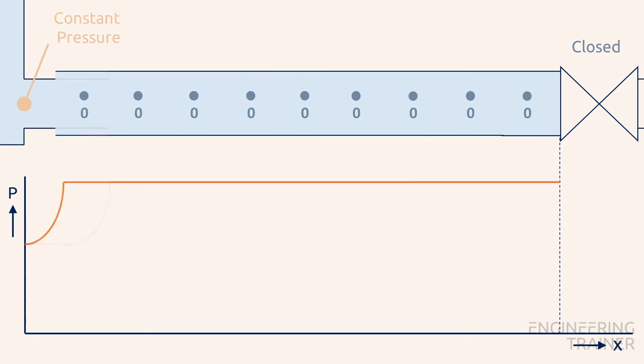Once the pressure wave reaches the reservoir it cannot continue because of the constant pressure from the tank. The situation now shows a higher pressure in the pipe than that what is expected from the reservoir value. As a result of this pressure difference the water will start flowing from the high pressure region in the pipe to the lower pressure at the inlet, so back to the reservoir.